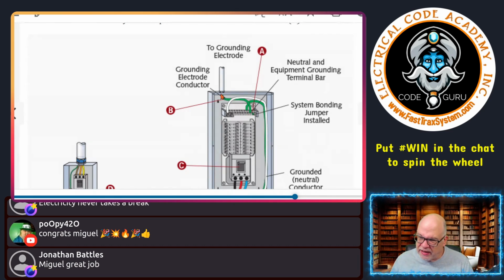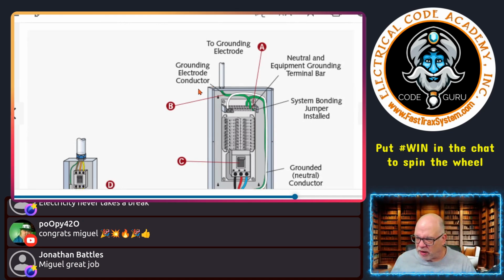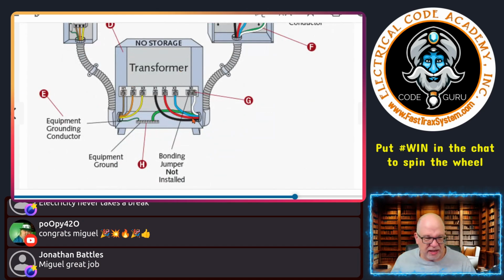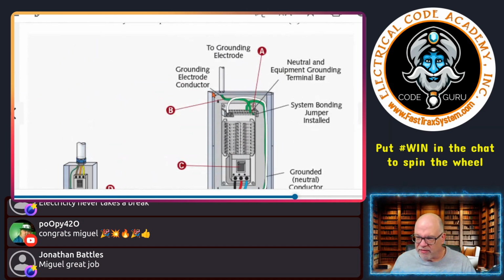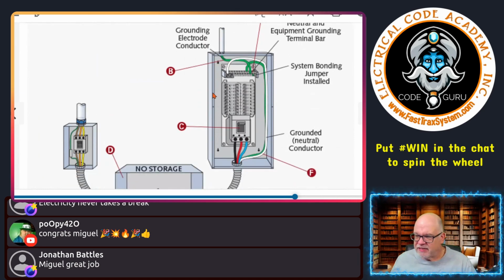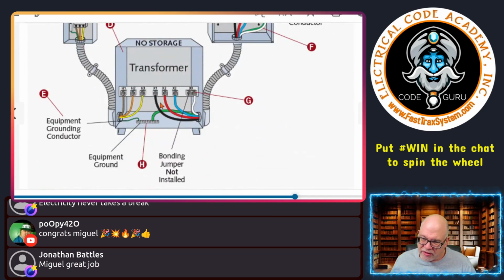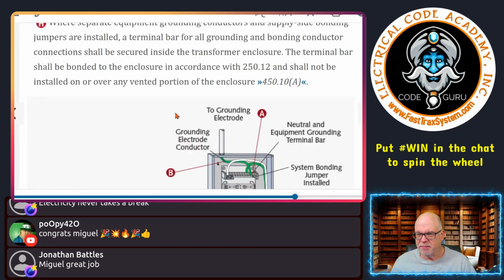So here you see what? That is where the grounding electrode conductor that's going out to whatever the electrode is for that structure, that's going out to it, okay? Or anything that extends that connection, right? So that's what it's doing right here. That's why it's here, okay? And you don't see it here, okay? Wherever that connection is being made, okay? Typically, the system bonding jumper is installed in here. And so typically out of here is where you're going to see them take this out, okay, and go out to the electrodes, okay? So important, where is the system bonding jumper being installed, okay? Important aspect of it.